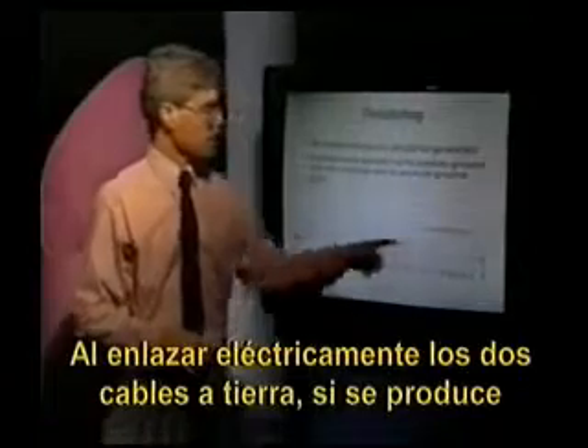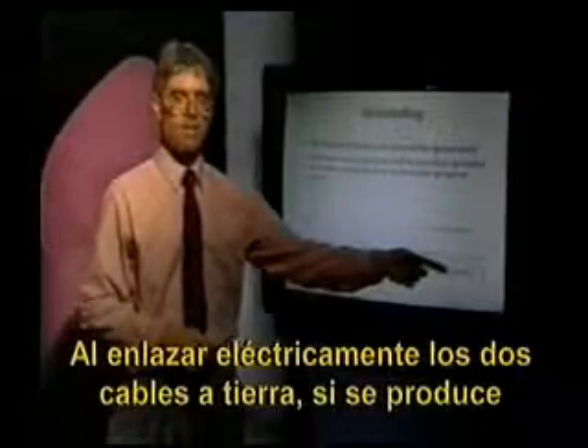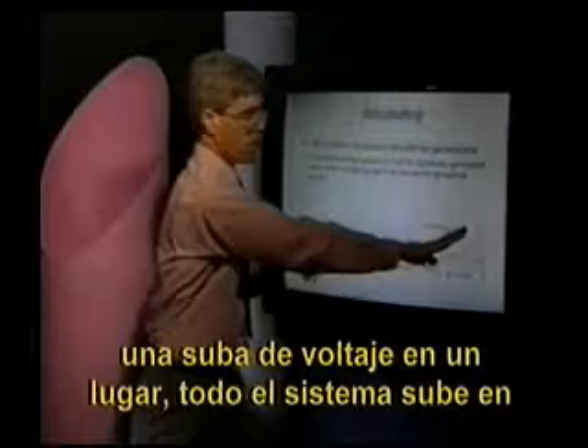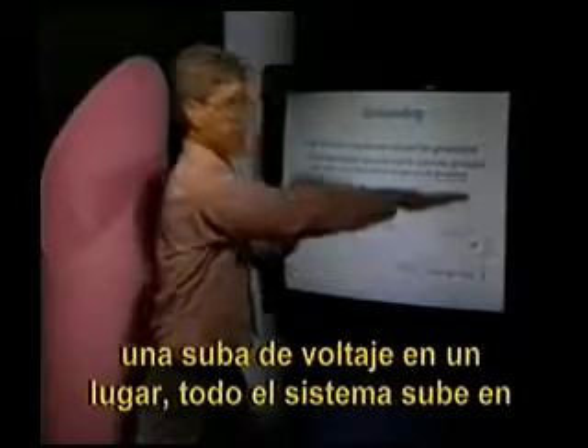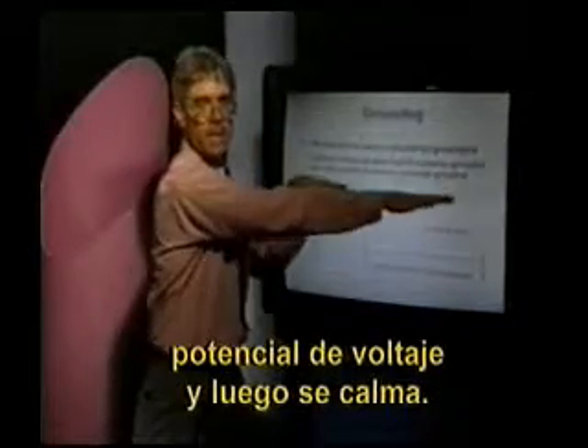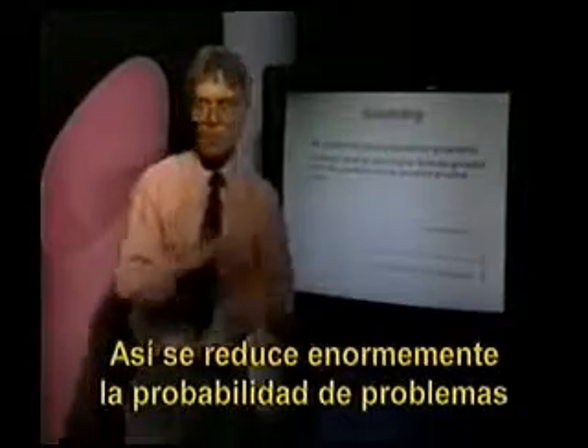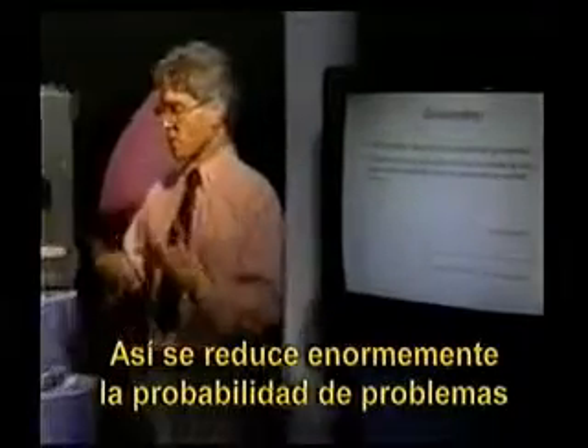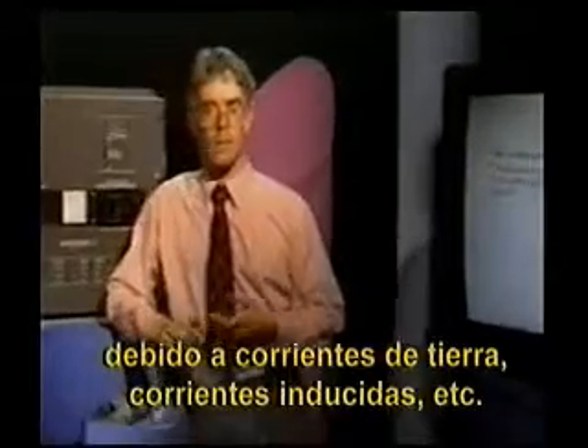By electrically bonding the two ground wires together, if there is a voltage rise in one place, all of the system rises in voltage potential and then settles down. And the probability of problems due to ground currents and induced currents and so on is greatly reduced.